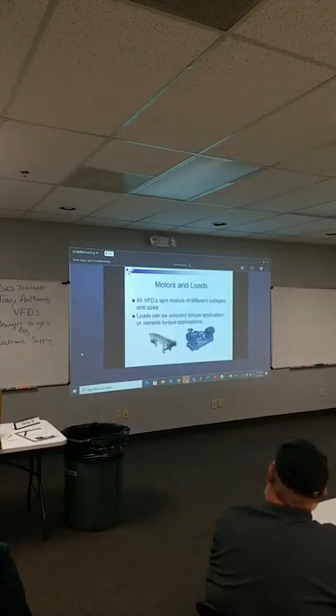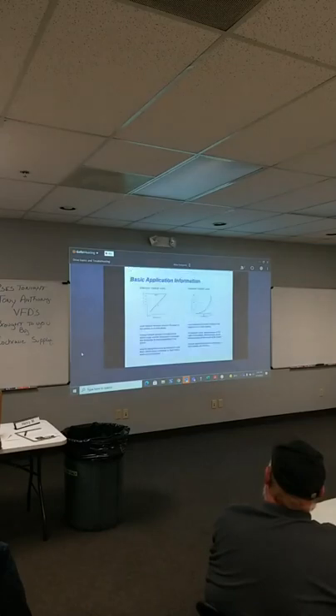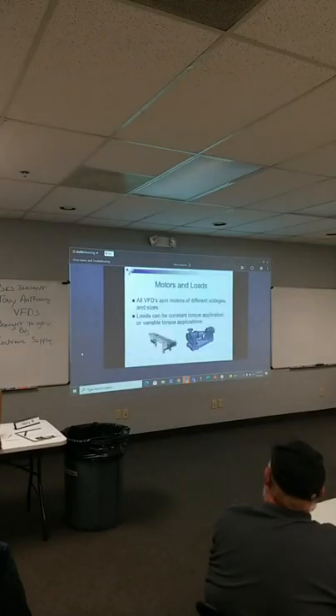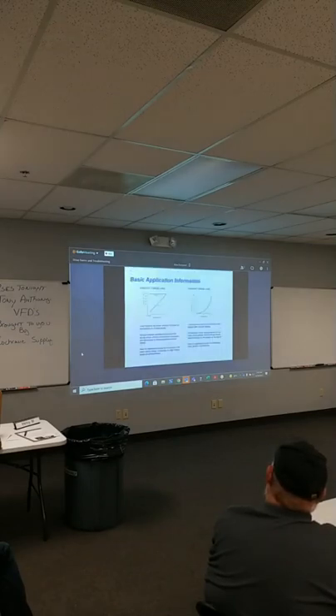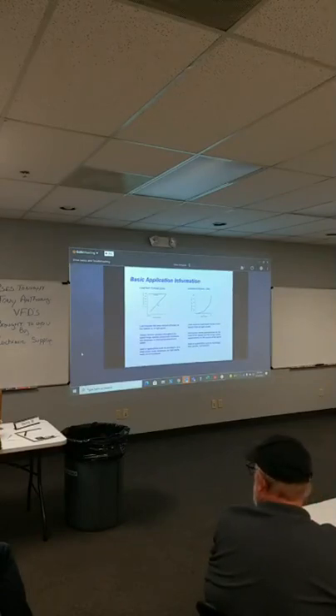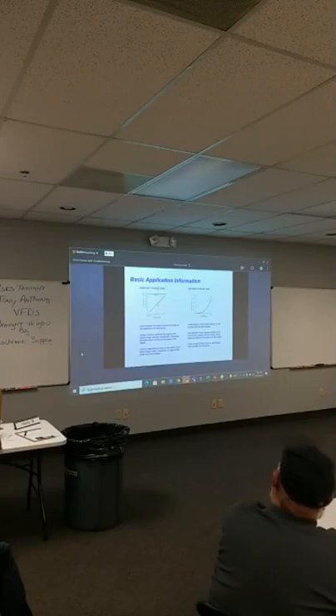All right, move through this. Motors and loads. I'm going to cover this real quick because y'all deal mostly with variable torque loads. There's basically two types of loads out there, and the ones we see in the industrial world are called constant torque, like a conveyor. You can see right here in these curves, constant torque: no matter if the conveyor is running 100 feet a minute or 1,000 feet a minute, the torque required to move that conveyor is based off the load on the conveyor. But a variable torque load is your world, which would be centrifugal pumps and fans.